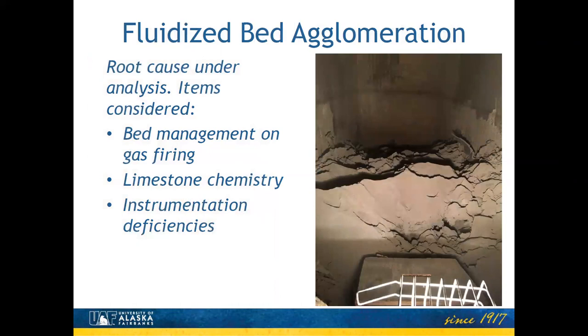Then this is the fluidized bed agglomeration. You're looking in through the bottom door of the furnace there, and in normal conditions, that would be a flat level of sand and ash. And it would just look perfectly flat. What had happened was the glassification of some of the material in there, and it occurred after a period of time that we were running on the natural gas burners for a few days.